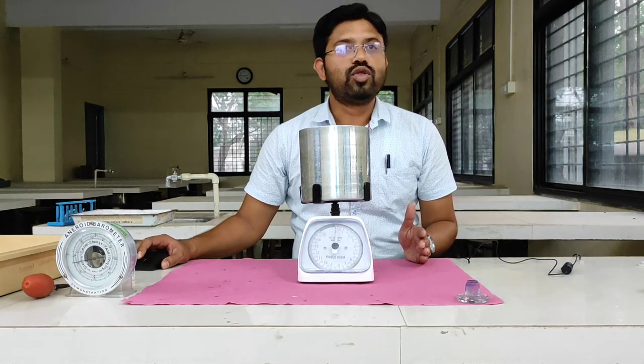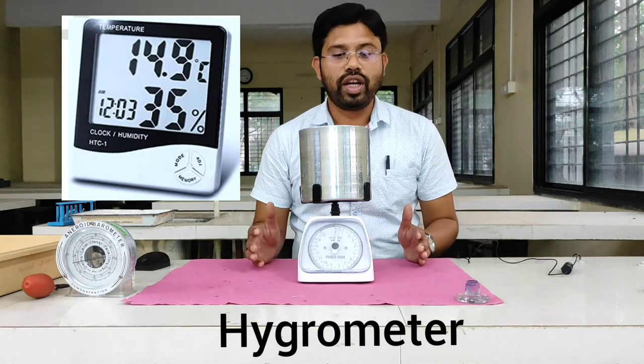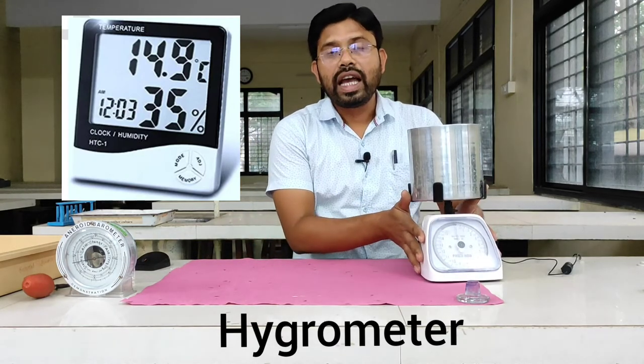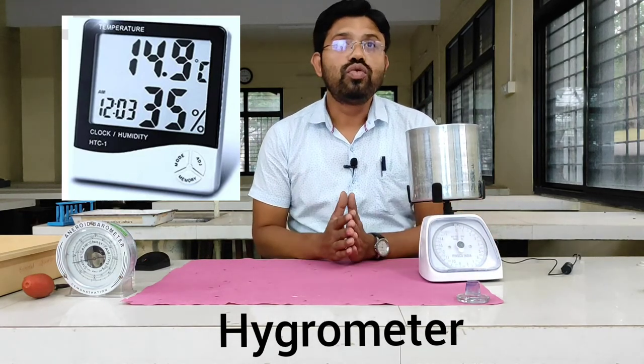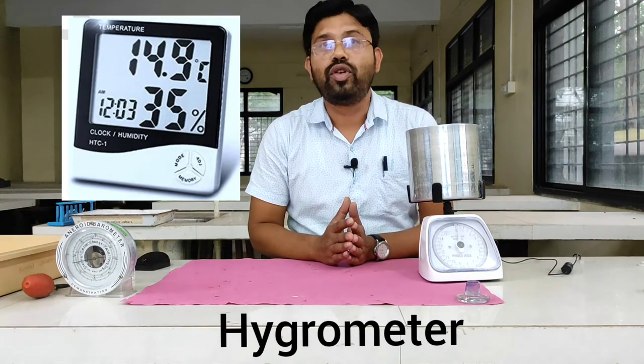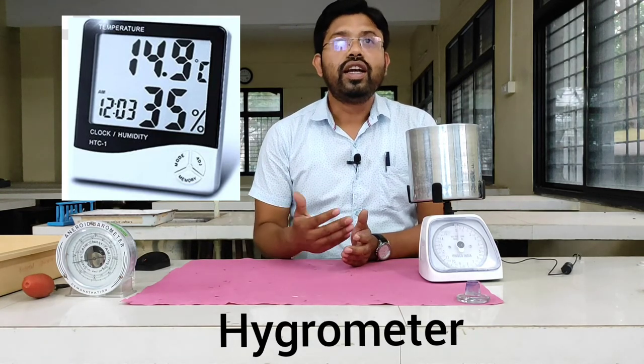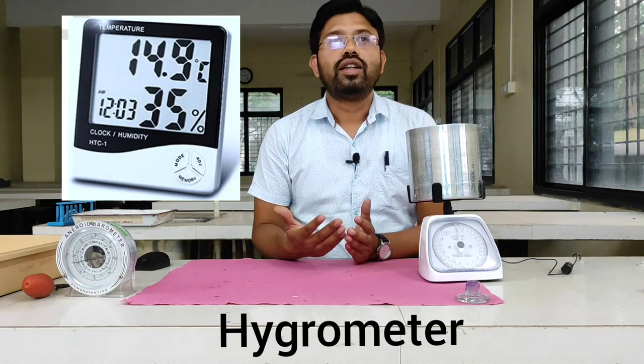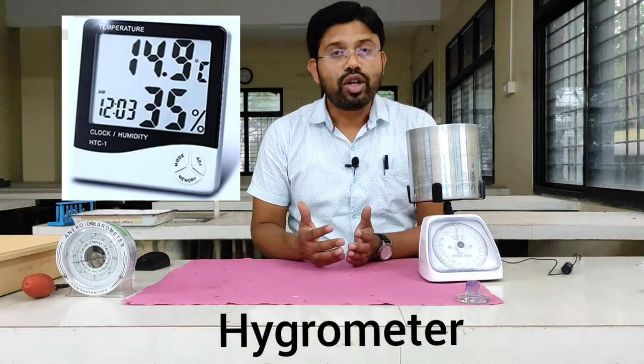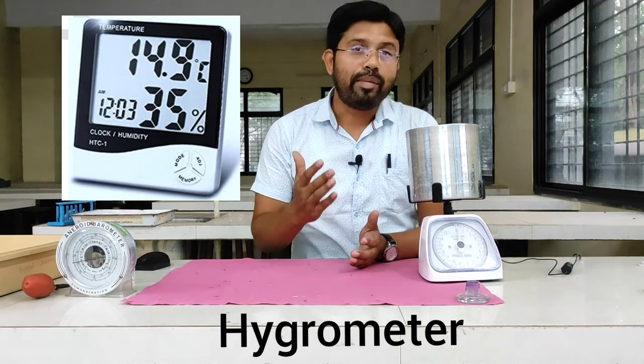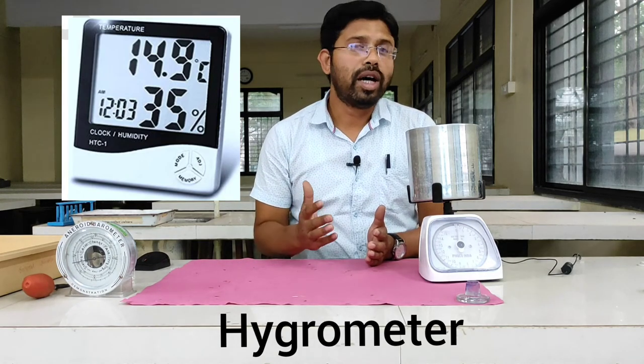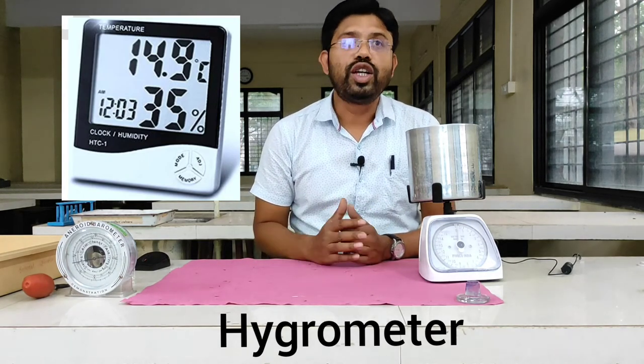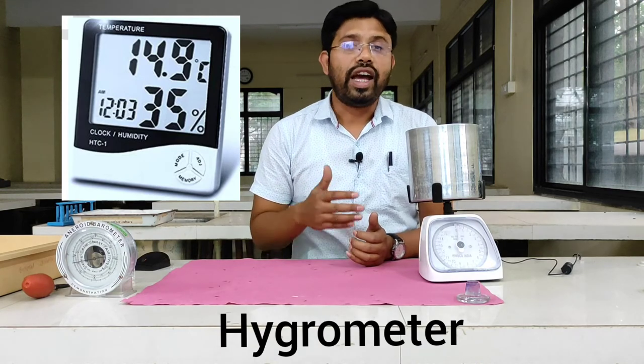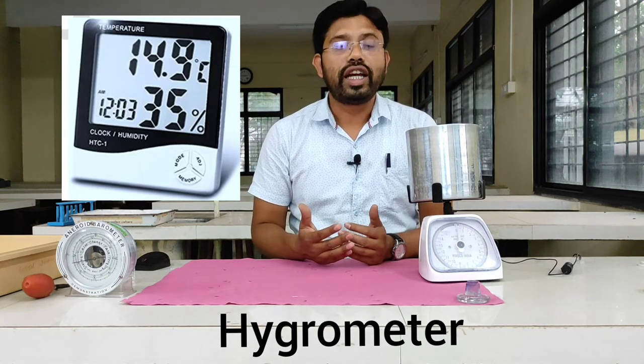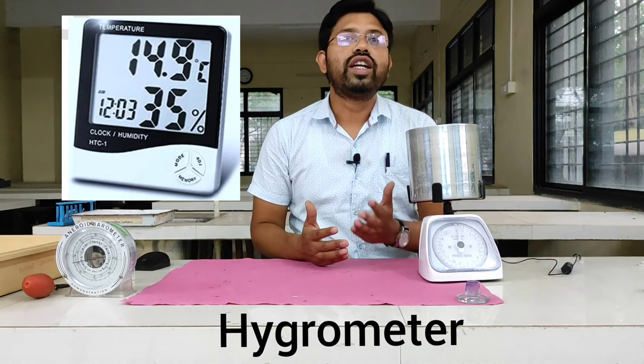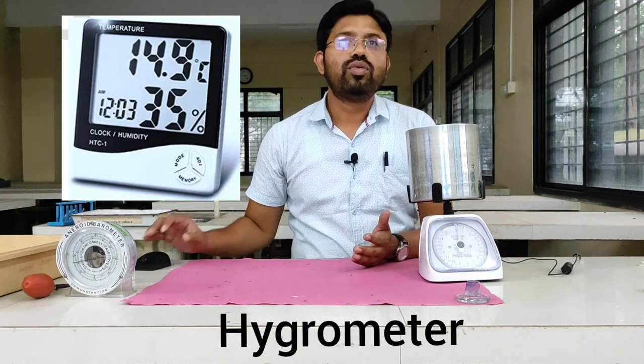Now we will take another instrument, the hygrometer. What is a hygrometer? It is an instrument used for measuring the moisture content in the environment. Humidity measuring instruments usually rely on the measurement of other quantities such as temperature, pressure, mass, and mechanical or electrical changes in substances. As the moisture is absorbed, through calibration and calculation, these measured quantities can lead to the measurement of humidity.